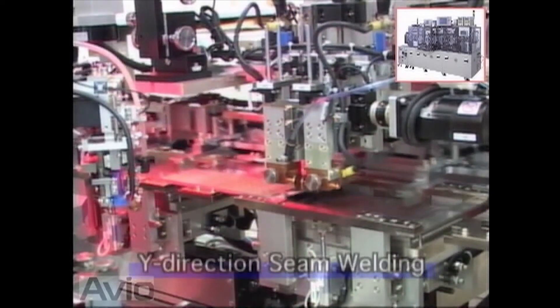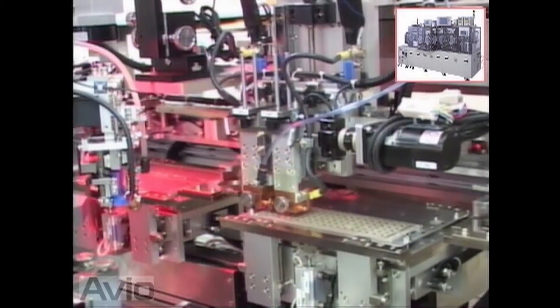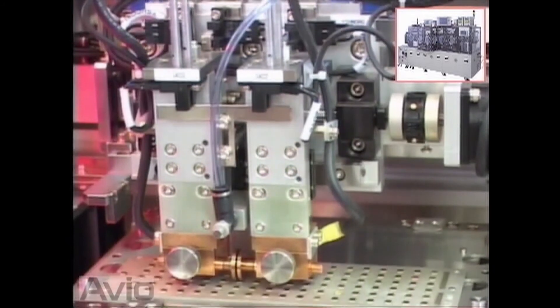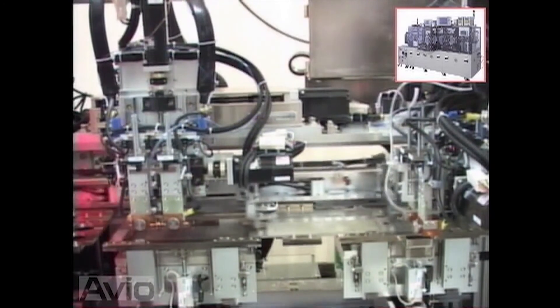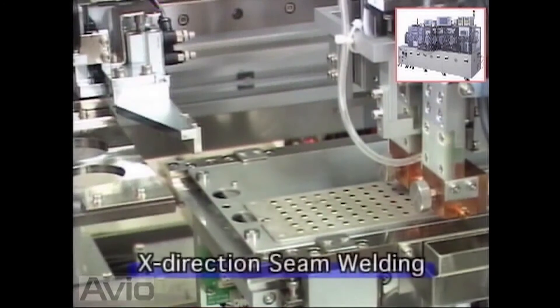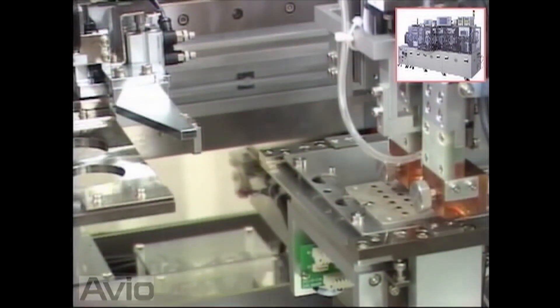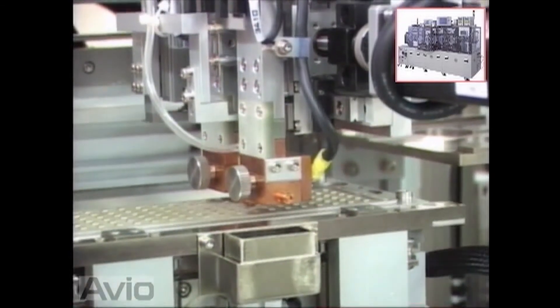In this process, the Y-direction among four sides of a package is seam welded. The electrodes roll along the edge of a lid and spot weld at specified spacing so there will be no gaps in between. In the next process, the remaining X direction sides are seam welded. Now all four sides of a package are hermetically sealed and an optimal environment for the device is maintained for many years.